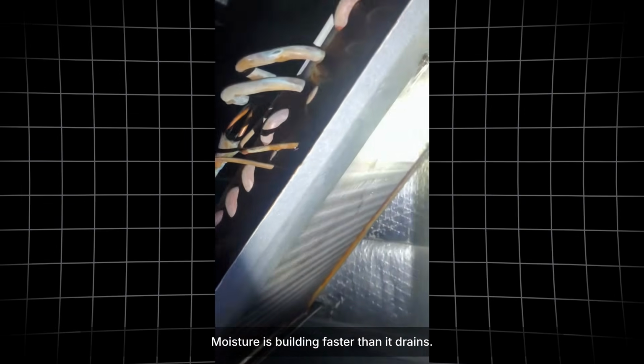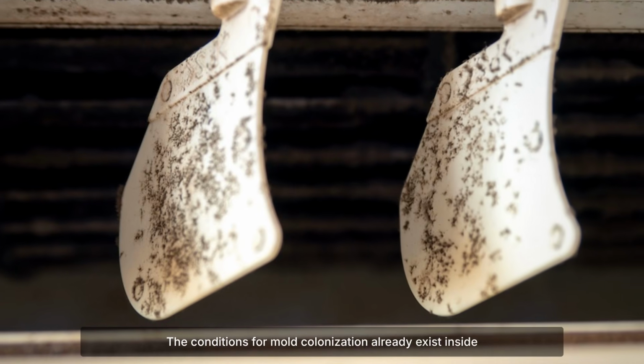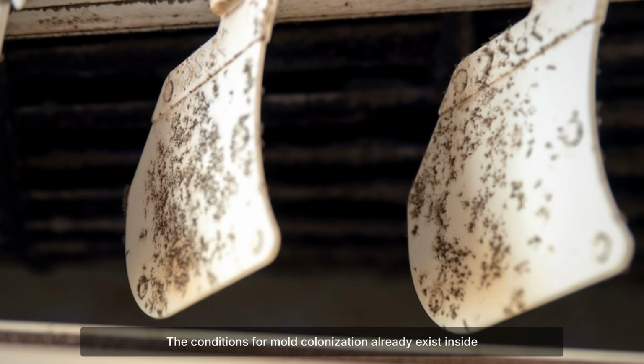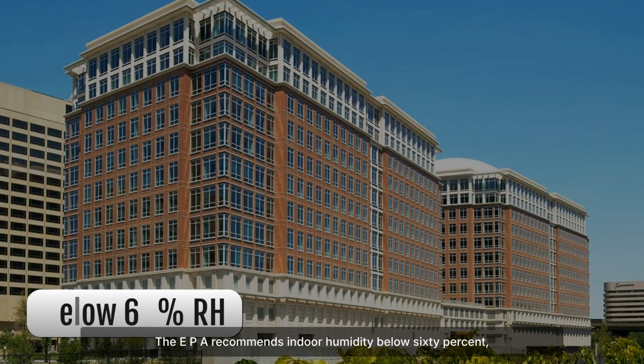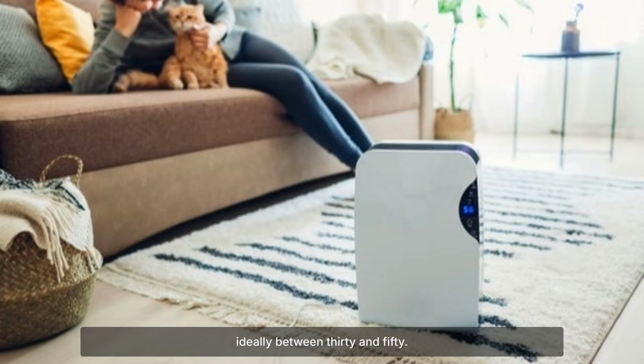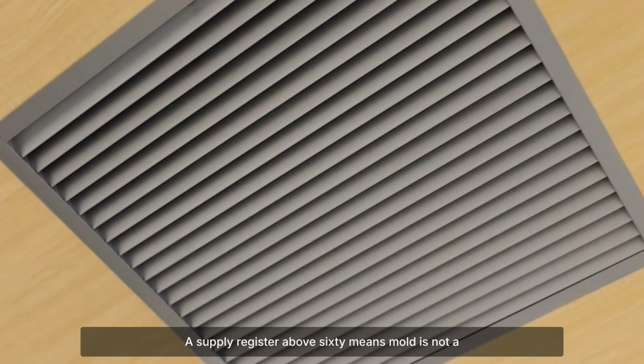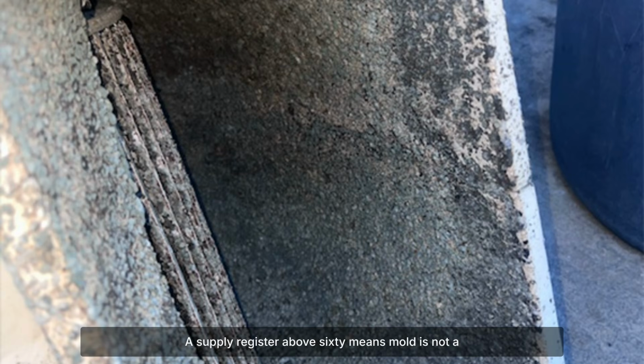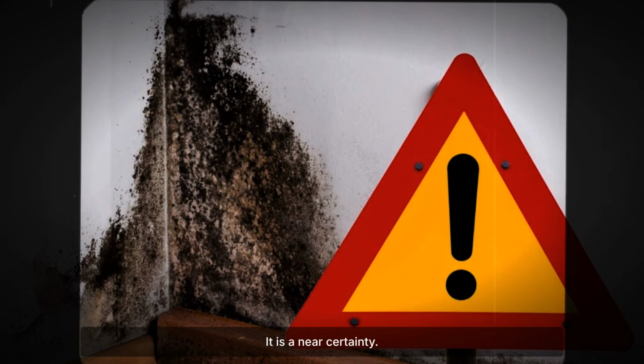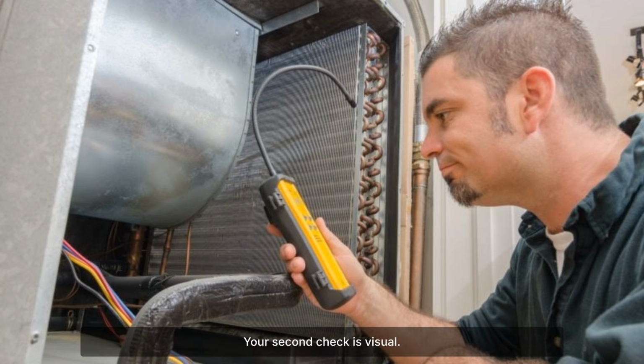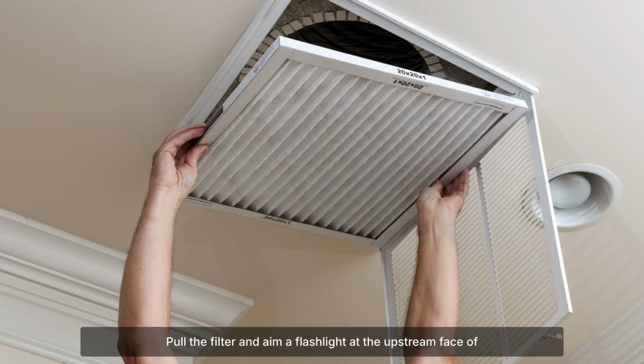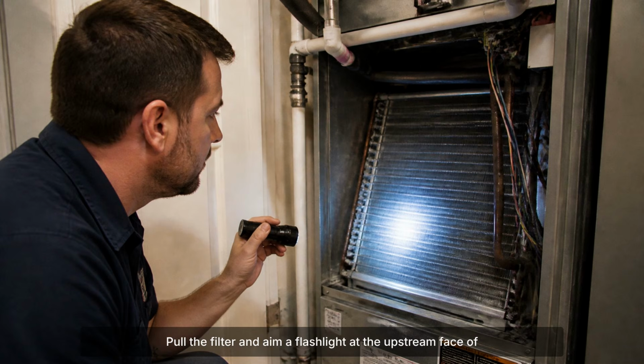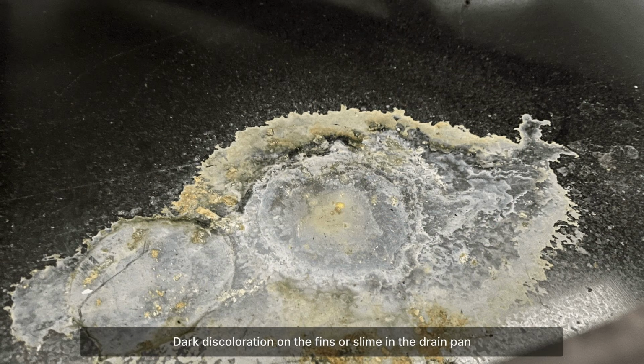Moisture is building faster than it drains. The conditions for mold colonization already exist inside your air handler. The EPA recommends indoor humidity below 60%, ideally between 30 and 50. A supply register above 60 means mold is not a possibility, it is a near certainty. Your second check is visual. Pull the filter and aim a flashlight at the upstream face of the evaporator coil. Dark discoloration on the fins or slime in the drain pan confirms active growth.